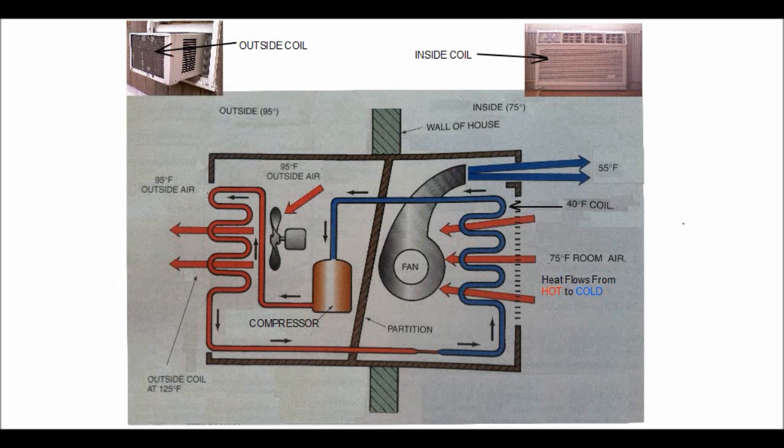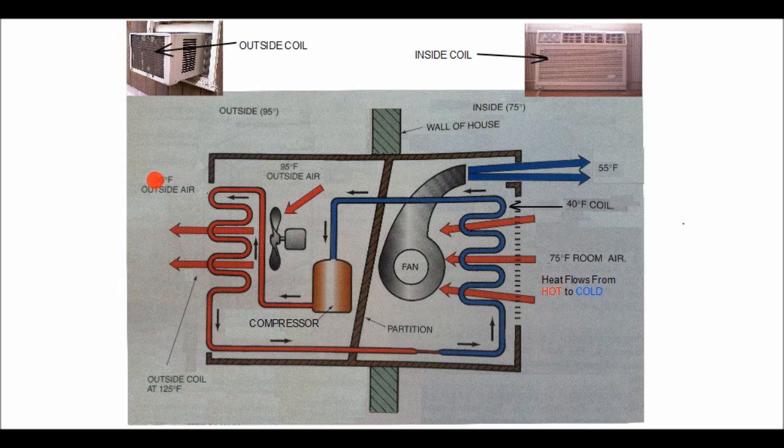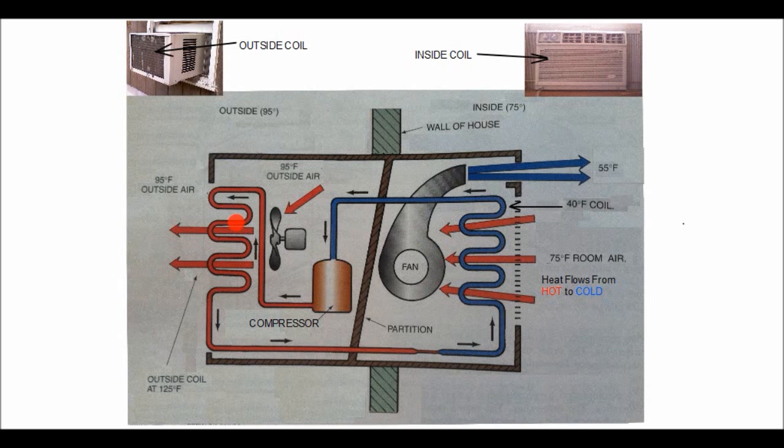Now remember that heat flows from hot to cold, so we have 125 degree refrigerant flowing through this coil. The outside air is 95 degrees, so the heat in the refrigerant in the outdoor coil will flow out of the coil and into the outside air.